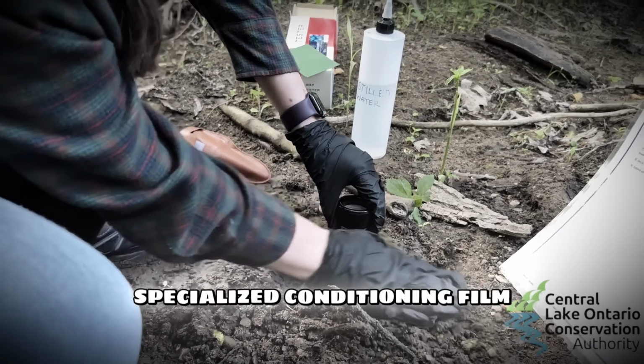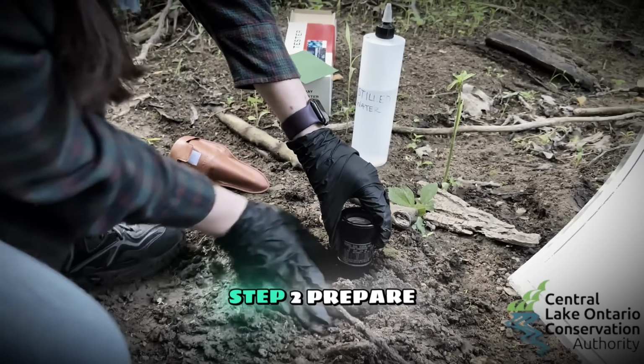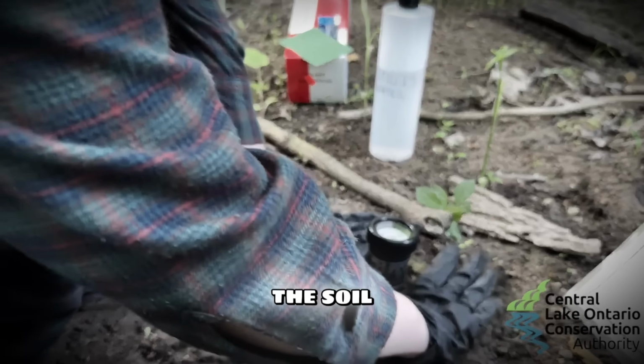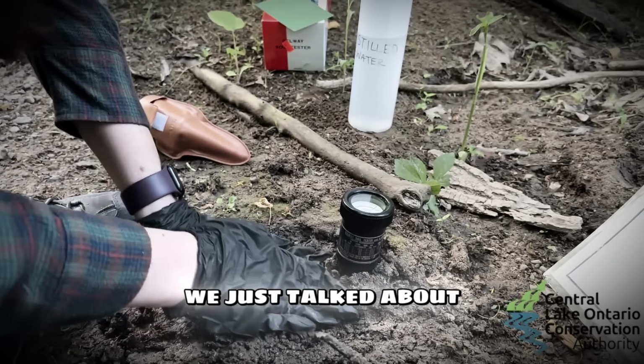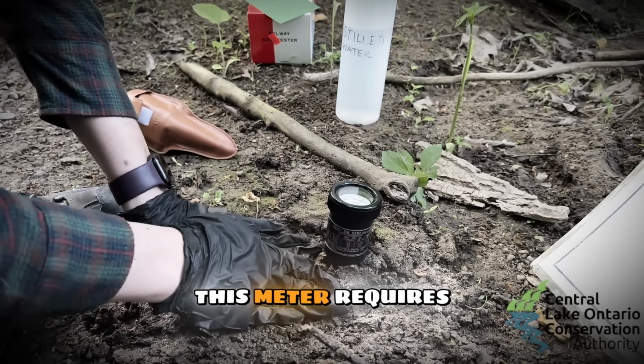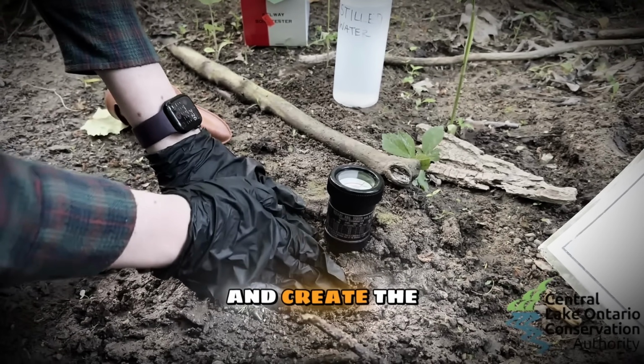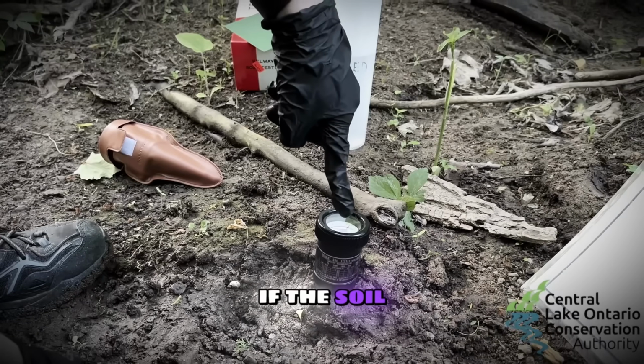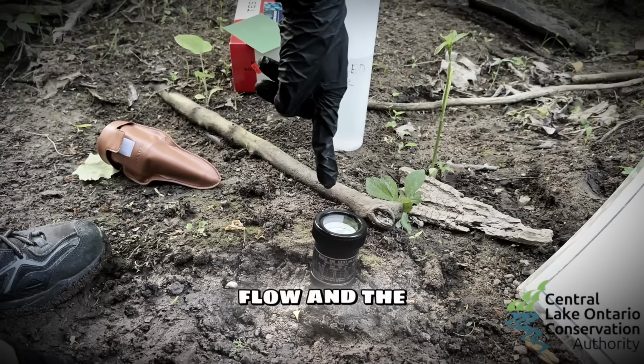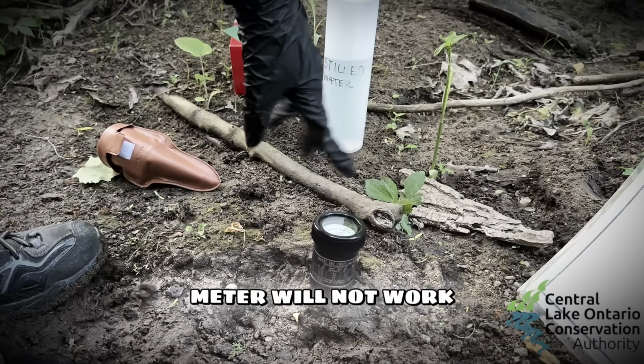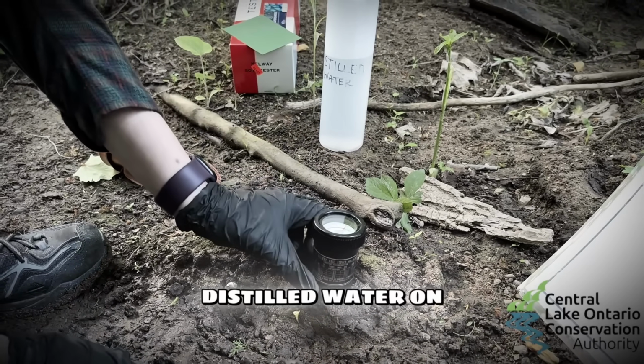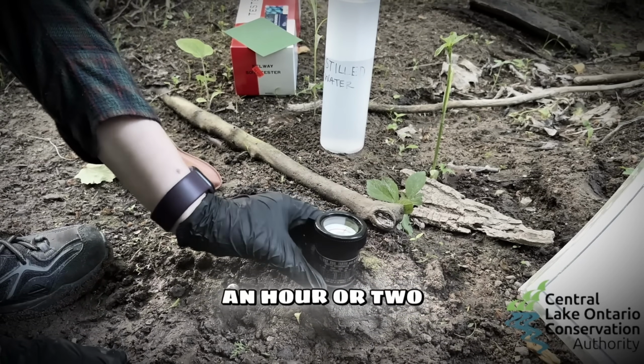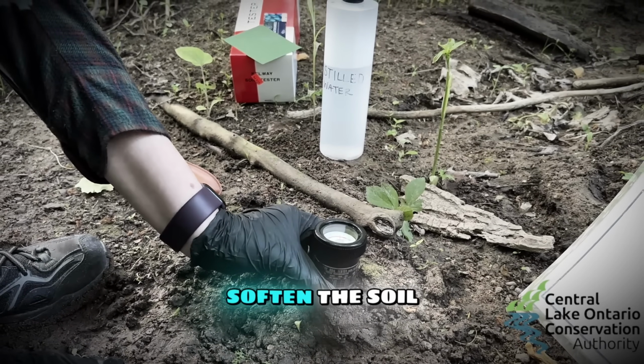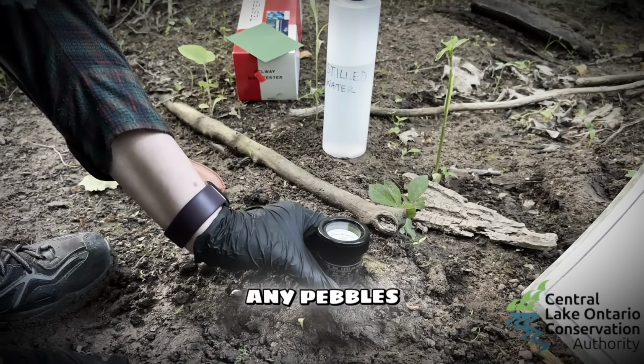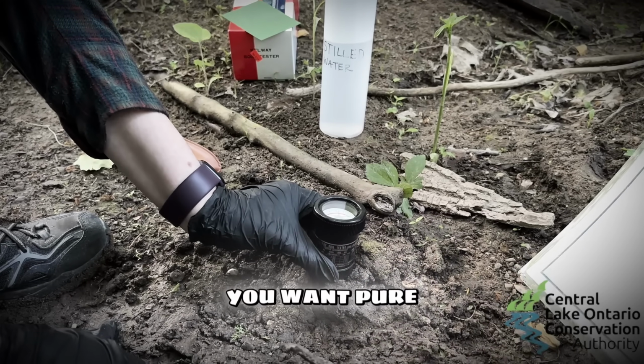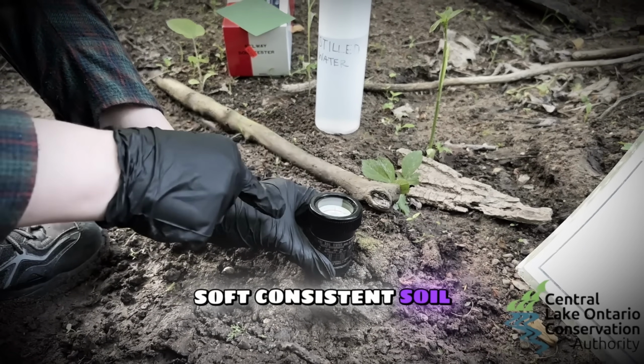Only use the specialized conditioning film. Step 2, prepare the soil. Remember the science we just talked about? This meter requires moisture to act as an electrolyte and create the electrical current. If the soil is bone dry, no current can flow, and the meter will not work. If the ground is dry, pour a little distilled water on the area and wait about an hour or two. Once damp, soften the soil and carefully remove any pebbles, grass, or leaves. You want pure, soft, consistent soil.